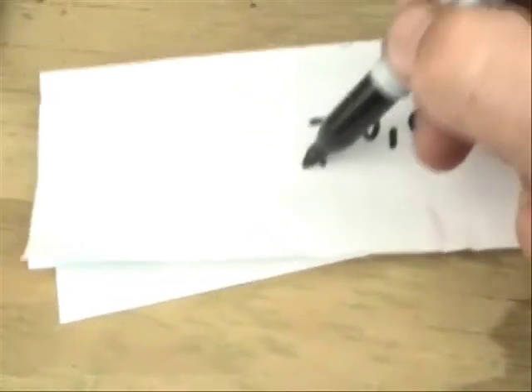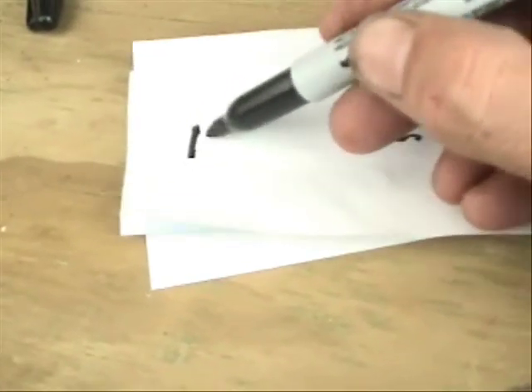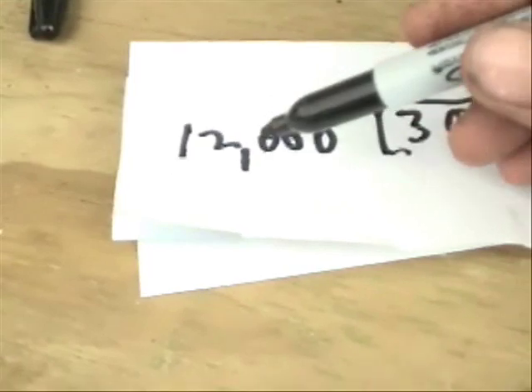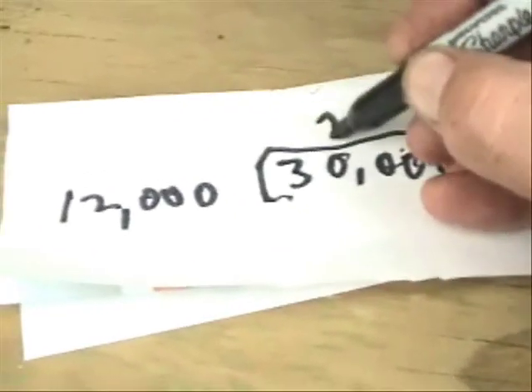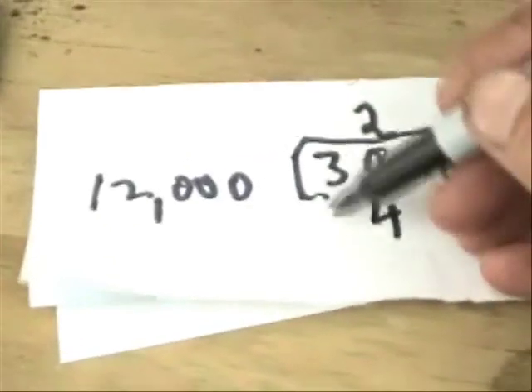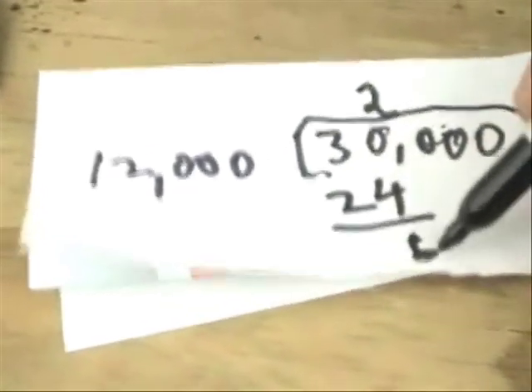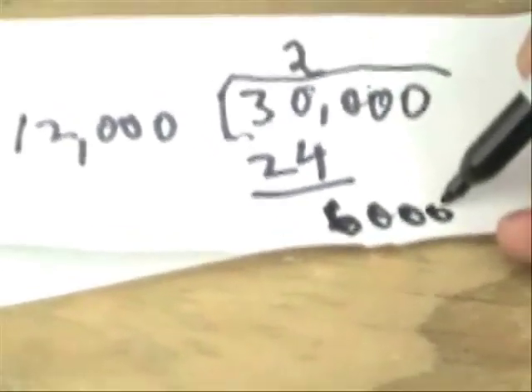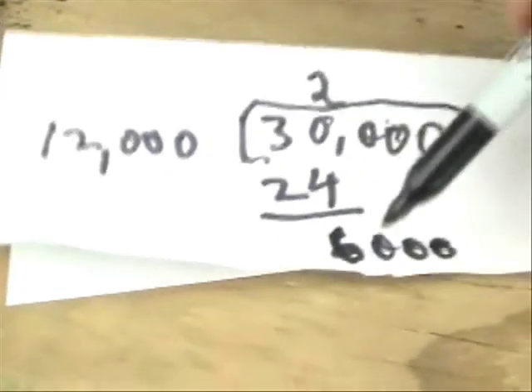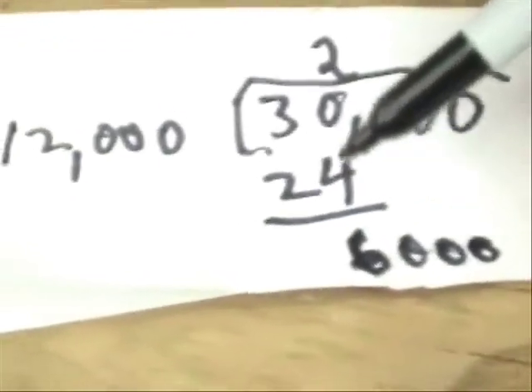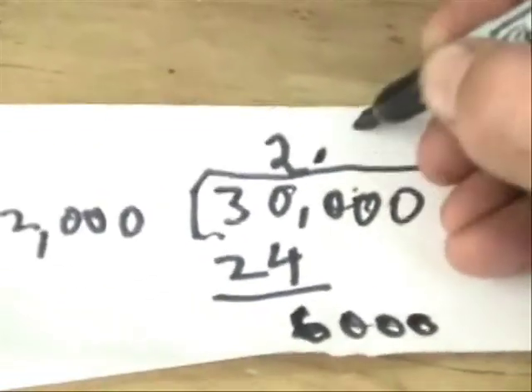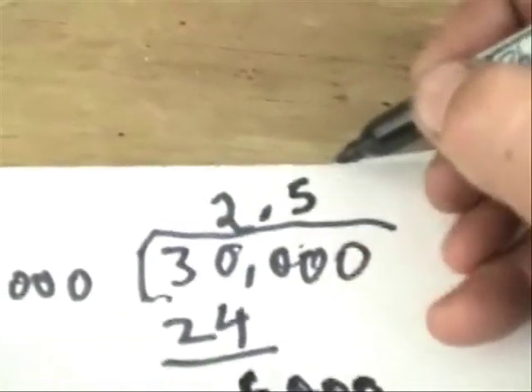What we have is a 30,000 BTU system, and we'll divide that by 12,000, because there are 12,000 BTUs to a ton. That's going to go at least 2 times. Our remainder is 6,000 BTUs — and 6,000 is half of 12,000 — so what we really have is a two-and-a-half ton air conditioning system.